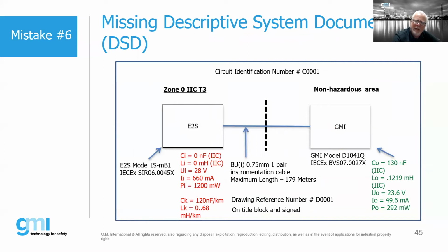So what we can do in a situation like this, and I had this question not too terribly long ago, a client had a particular GMI barrier in conjunction with a transmitter. It was basically 30 different units, but they were all the exact same units. Same barrier, same transmitter. Did they have to actually generate 30 different drawings? And I said, well, depending on how you want to do it, you could have one drawing with 30 different tags if you want to do that. My suggestion would be just replicate the drawing and give it drawing number 1, 2, 3, 4, 5, 6, 7, 8, whatever it is.